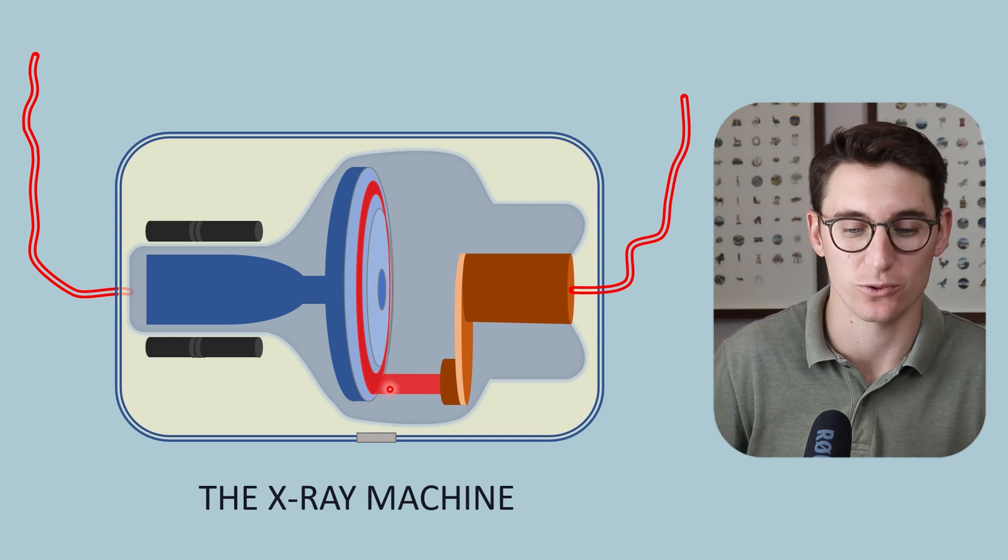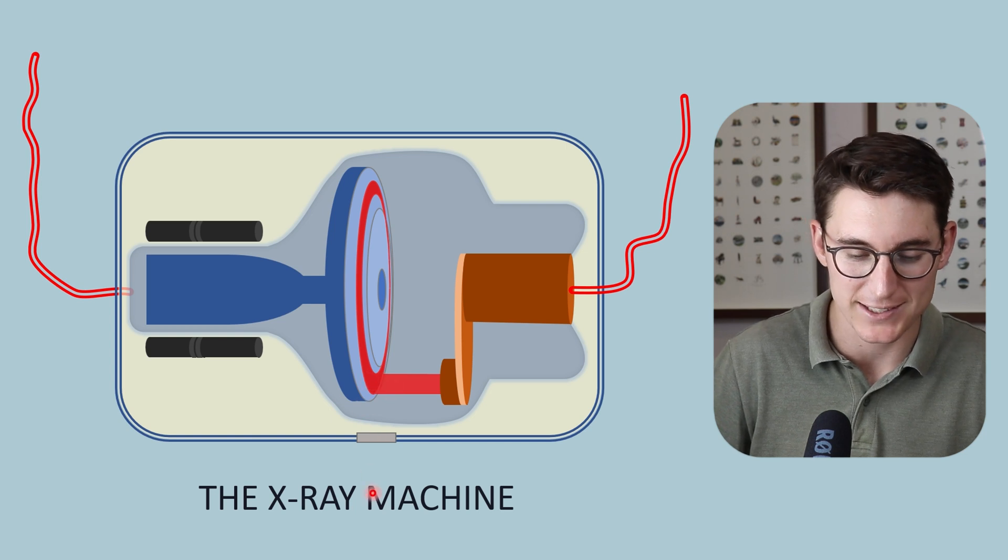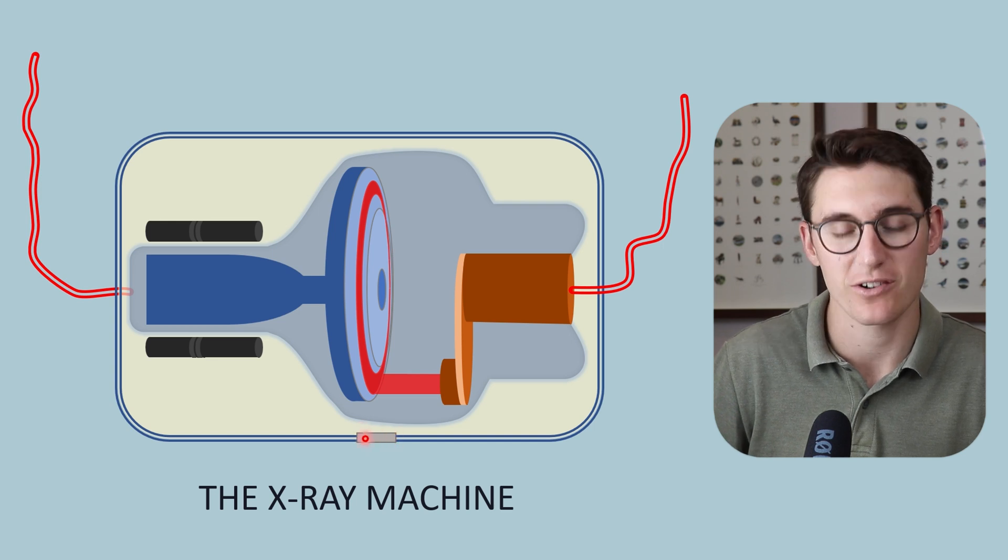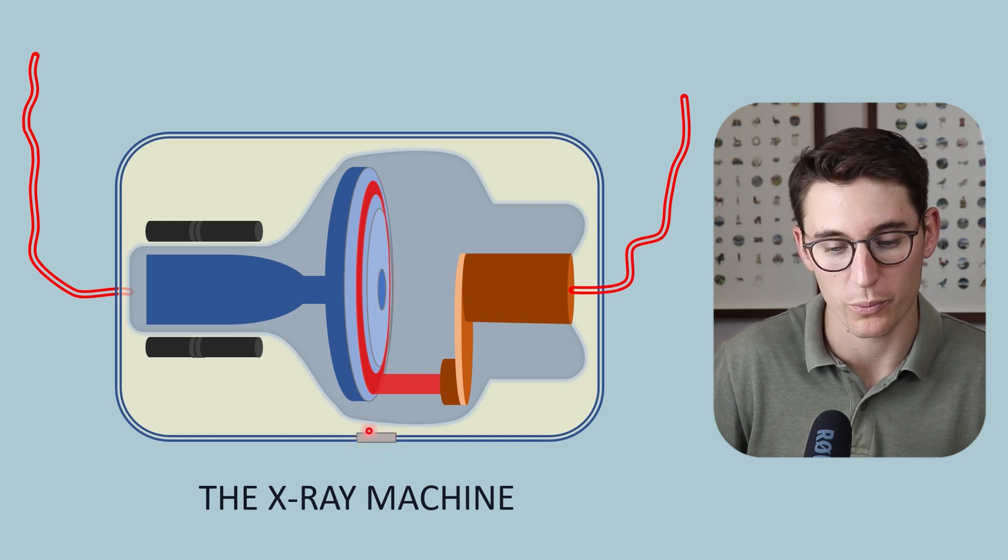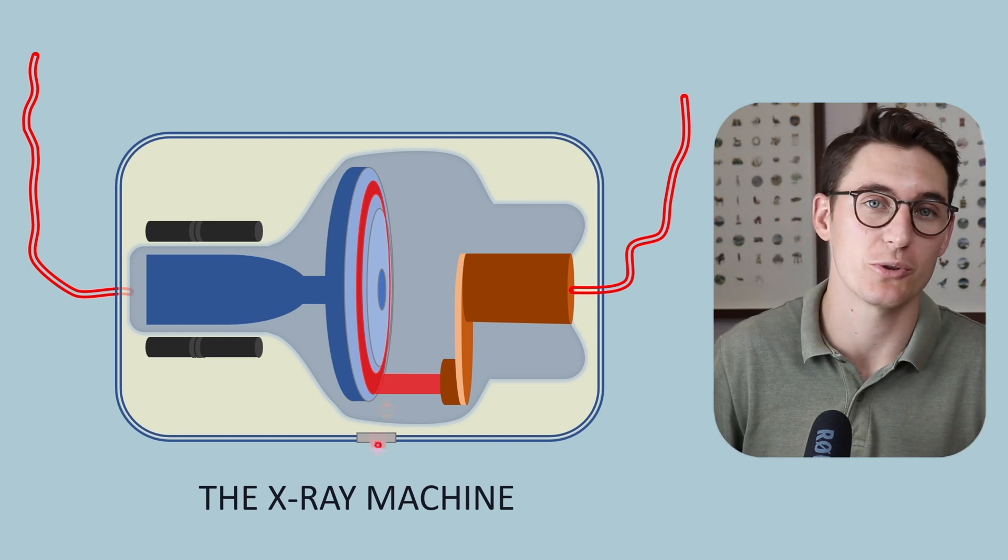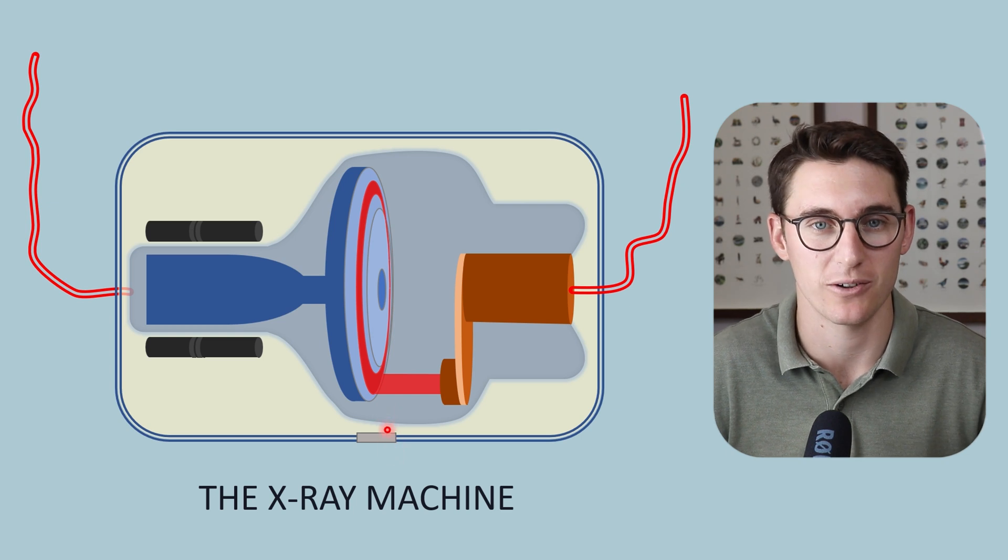Now x-rays are produced at this actual focal spot, and they will exit the x-ray tube through an x-ray window here. This x-ray window is generally made up of aluminium or beryllium, and it filters out some of the lower energy x-rays that are going to contribute to our patient dose, but not to our image.